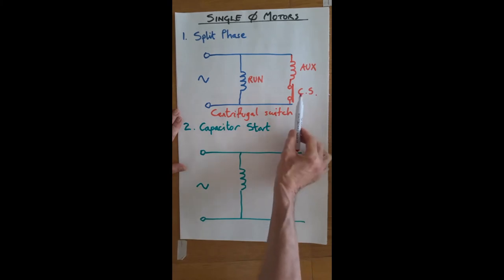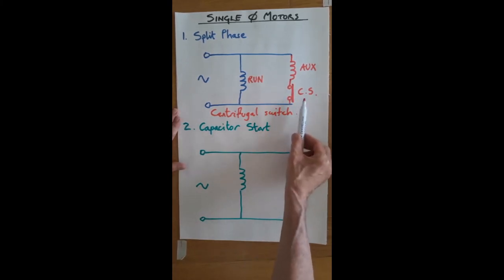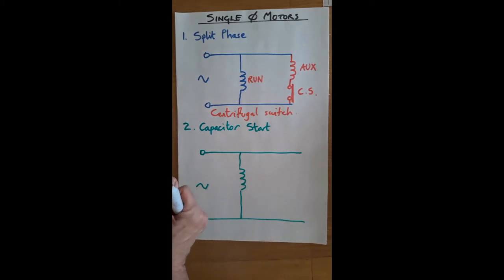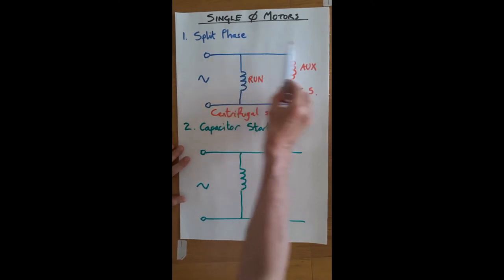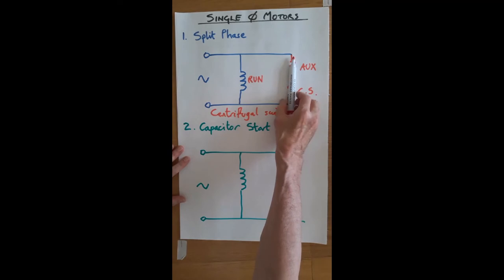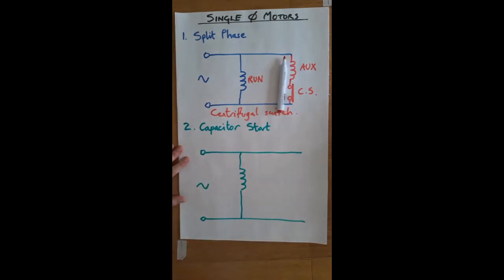Okay, so the centrifugal switch works on rotational speed. The faster it goes, then what will happen is as the motor reaches a particular speed, the contacts will open and take this out of circuit. So coming back to these two windings in the motor, the run winding and the auxiliary winding are mounted at 90 degrees to each other.